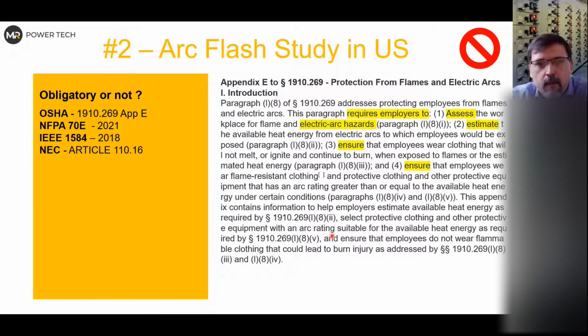1910.269, Appendix E. And there is also a second table there saying what kind of method is applicable to what kind of voltage levels. You also have it written now in the NEC, the National Electrical Code, in Article 110.16, and in IEEE 1584 and NFPA 70E. So probably you might fight over the word, is it obligatory or not? But I would say in 99% of cases in the US, you can treat it as obligatory. I'm not sure you can win in court by saying that you didn't do the study and you did something different. But in my feeling, it's much easier to follow the OSHA requirements and fulfill the NEC requirements and NFPA 70E just by doing the arc flash study or following the table method estimation than by not doing anything.